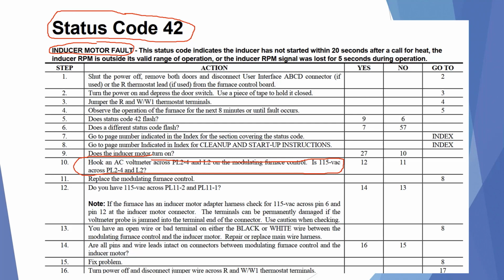Let me point out one other thing here. They ask you on this troubleshooting guide, are all pins and wire leads intact at the connectors? If you're using fat pins on your voltage meter and trying to shove those into these pins, you can do a lot of damage. Many times the fault is not with the inducer motor and the fault is not with the control board. It's with the plug, that the pins in the plug are not making contact. So always check your wiring harness to make sure that the wires are seated correctly and the pins are making good contact in those plugs.